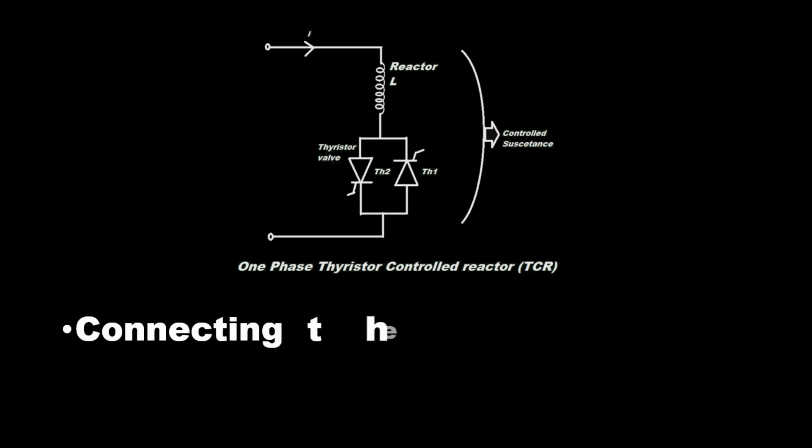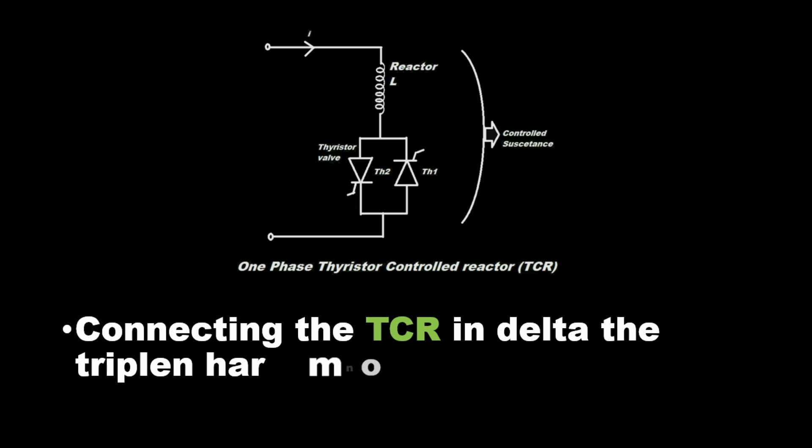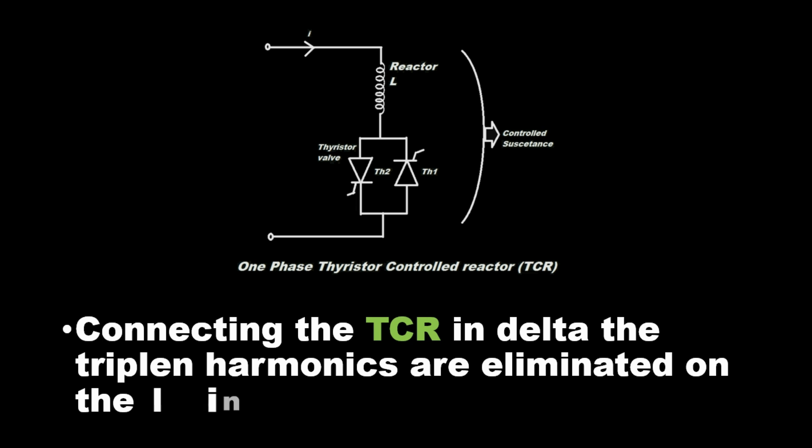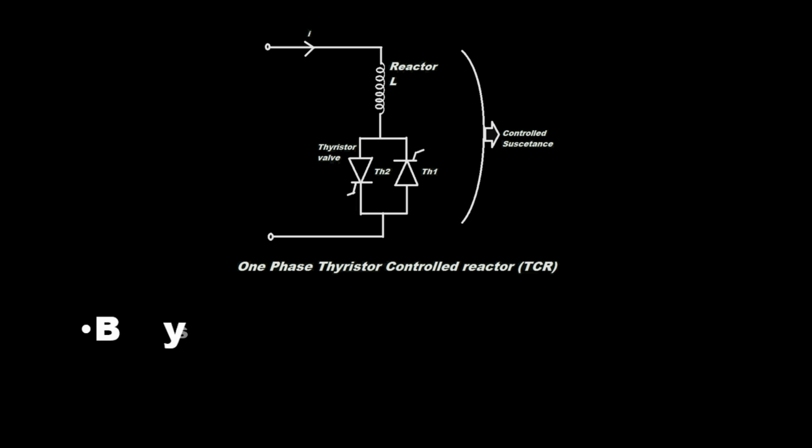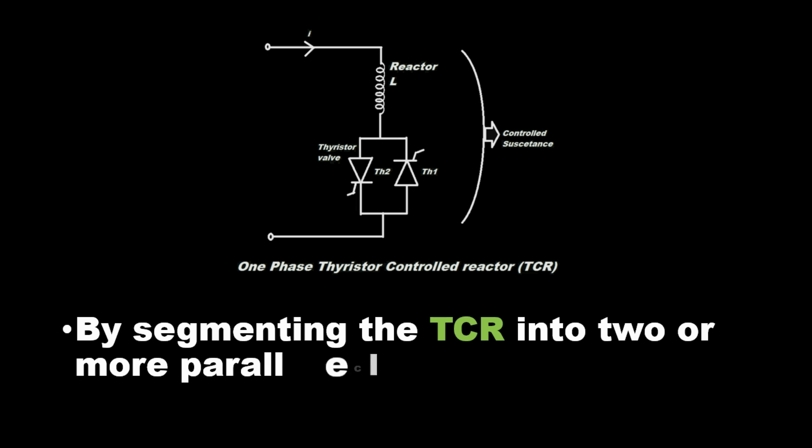Connecting the TCR in delta, the triplen harmonics are eliminated on the line side. By segmenting the TCR into two or more parallel connected branches, the harmonics can be reduced.